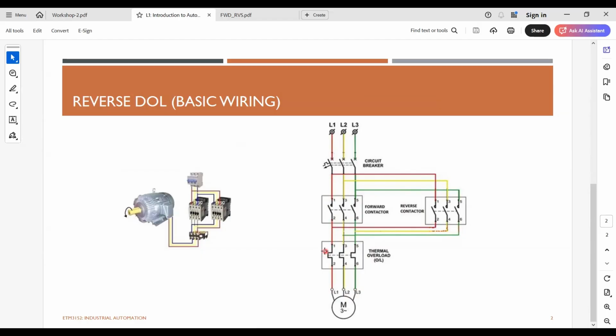And if you want to change the direction, as I mentioned, you need to change two terminals of the motor. So this is how it is done using an additional contactor. We call it a reverse contactor. Here you can see that the L1 phase comes to here and it again goes back to the L1 of the motor. So this line is not changed. It is the same as the previous line.